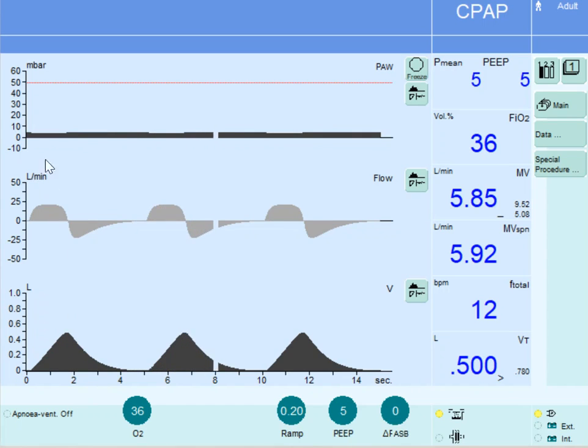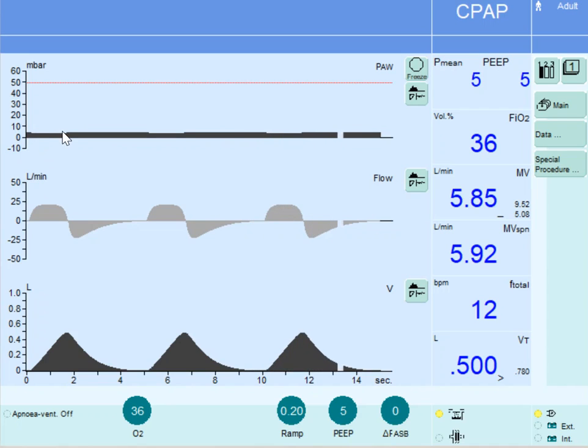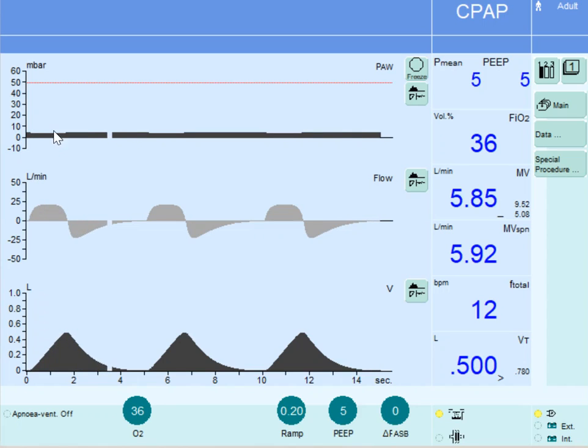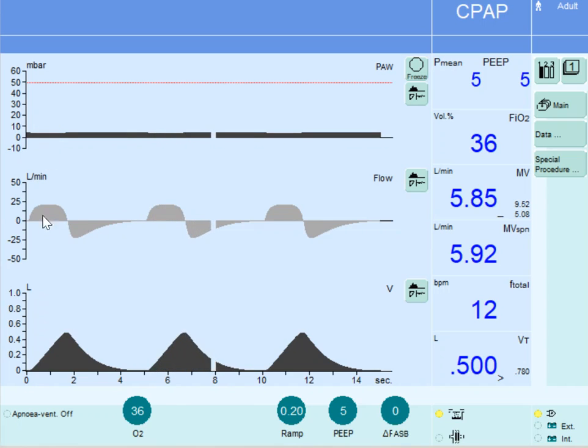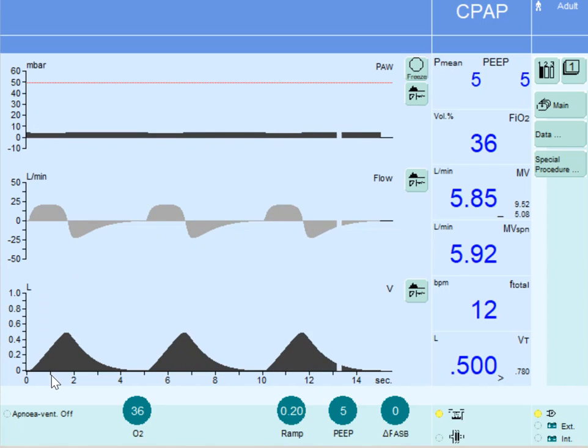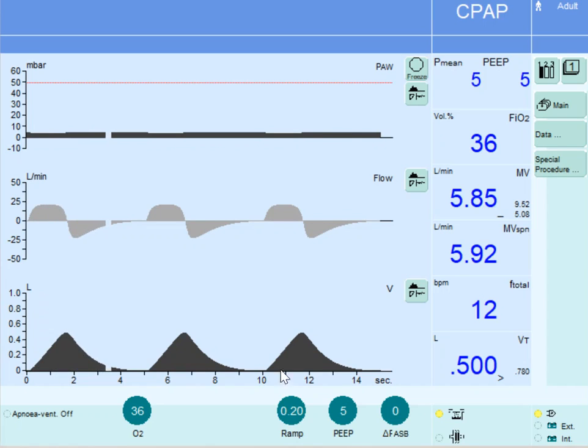Each breath is started by the patient and ended by the patient. The ventilator does not add any additional pressure above the level of CPAP. The flow is characteristically a sinusoidal waveform, and the tidal volume depends on the inspiratory muscle strength and the patient's efforts.